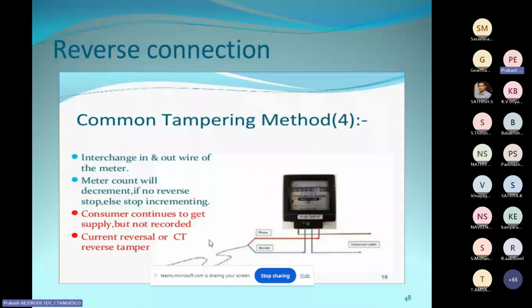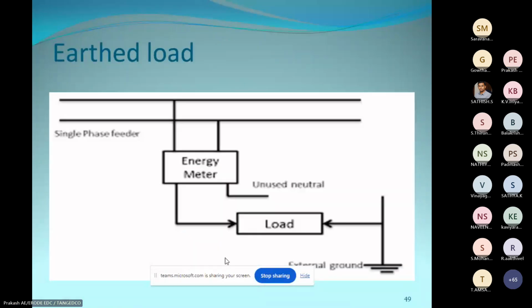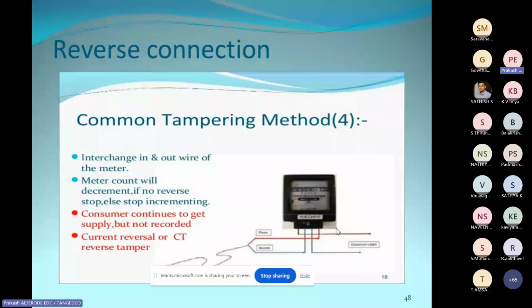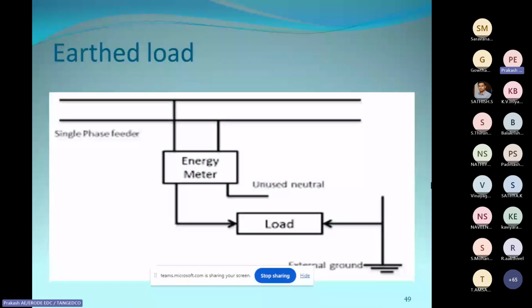So this is a seal we have zoomed in, a tampered seal. This is a common tampering method - you can see the interchange of the in and out wire, the red line and brown line. By reversing the in and out wire, they decrease and reverse the stop, causing a stoppage of the meter. This is called current reversal or CT reversal tampering, done by reversing the incoming and outgoing wire. This kind of thing will tamper the meter as well, through a reverse connection, and the load also gets affected - the unused neutral they will use.